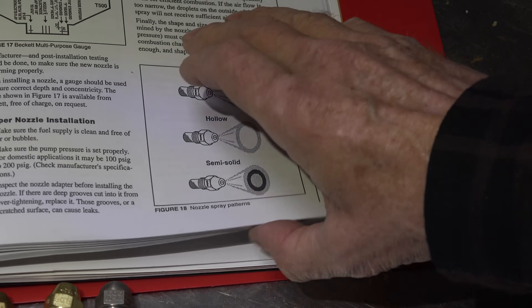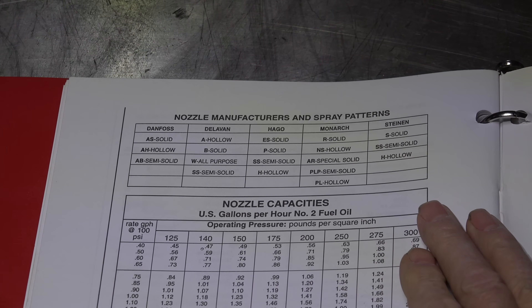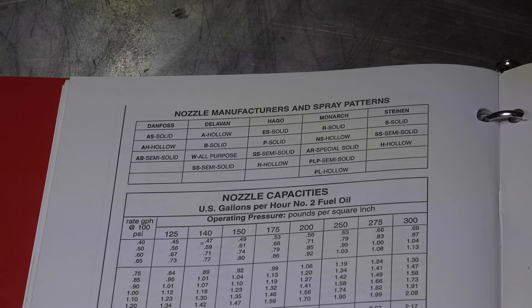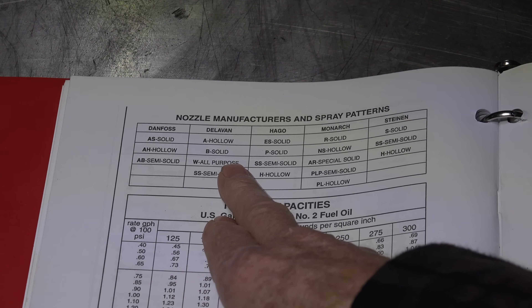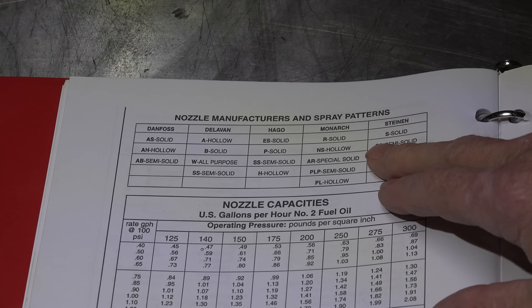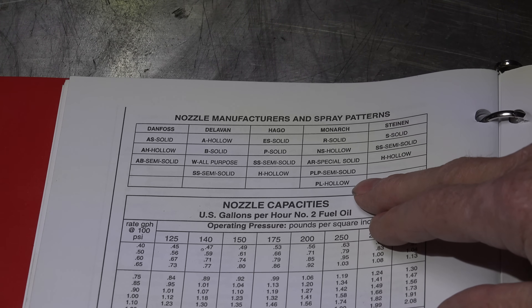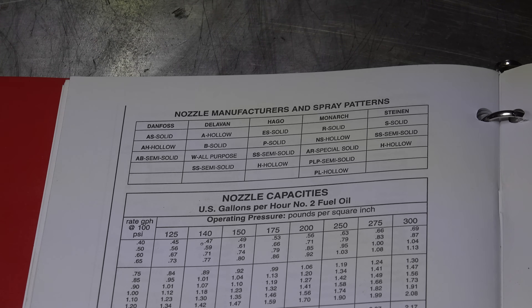Here are all the different manufacturers and what those letters and numbers mean. For Delavan: A is hollow, B is solid, W is all-purpose, and SS is semi-solid. For Monarch: R is solid, NS is hollow, AR is special solid, PLP is semi-solid, and PL is another type of hollow. They're all a little different. We've also got Hago, Danfoss, and Steinen in there.